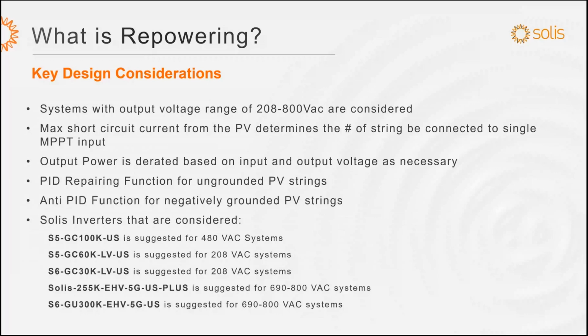For Solis inverters considered for repowering projects, there are about 5 models that we consider, and that's why the process is not simple. With one model, it's very difficult to accommodate all those repowering projects. The 5 models are the 100 kilowatt 480 volt, the 60 kilowatt 208 volt, the 30 kilowatt 208 volt, the 255 kilowatt 690 to 800 volt range, and the 300 kilowatt 690 to 800 volt range. Those are all the models we will be reviewing for how we can repower different central inverters.